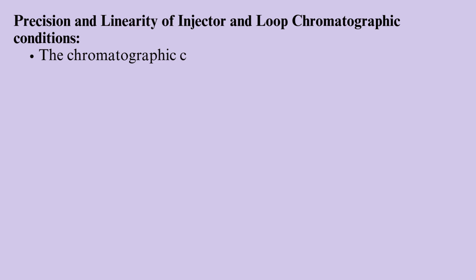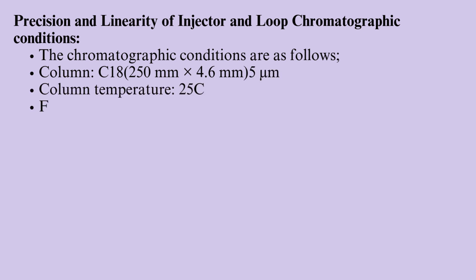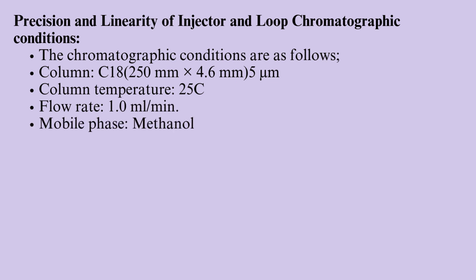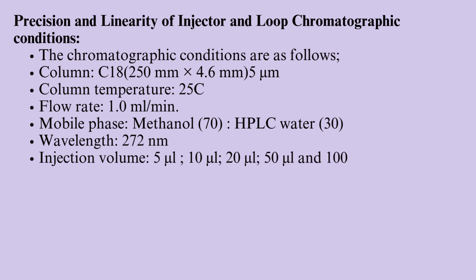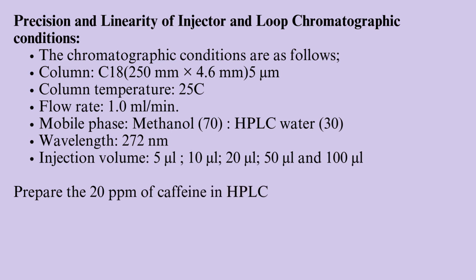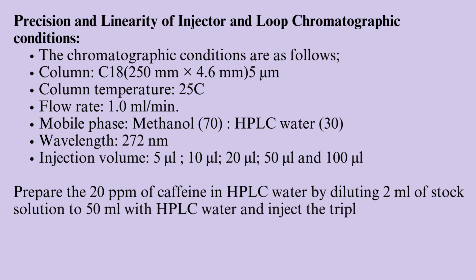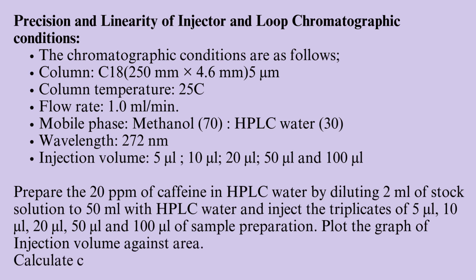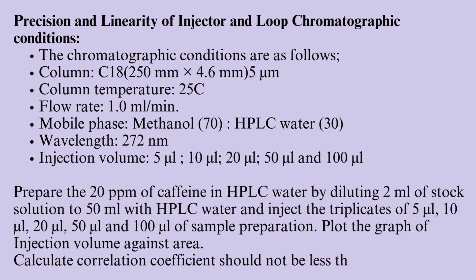Calibration of injector loop — precision and linearity of injector and loop. Chromatographic conditions: column C18, 250 mm × 4.6 mm, 5 µm; column temperature 25°C; flow rate 1 ml/min; mobile phase methanol/HPLC water; wavelength 272 nm; injection volumes 5 µL, 10 µL, 20 µL, 50 µL, and 100 µL. Prepare 20 ppm of caffeine in HPLC water by diluting 2 ml of stock solution to 50 ml with HPLC water. Inject triplicates of 5, 10, 20, 50, and 100 µL of sample preparation. Plot the graph of injection volume against area. Calculate the correlation coefficient — it should not be less than 0.998.